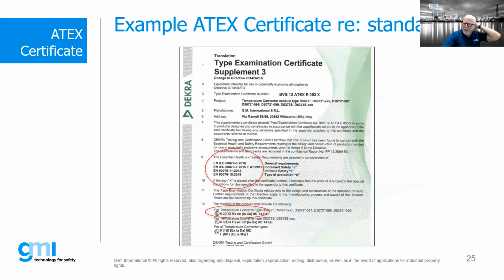Now, when we look at type examination certificates, this is kind of where Paulo was talking about. A lot of times the type examination certificates will actually have a lot of that prior information, and this might be at the very back of the original certificate. As Paulo said, you might get a certificate from a manufacturer that references the old ATEX directive or older standards. It's important to go back to the last pages, if you will, of your ATEX certificates - that's where you'll find the latest and greatest.